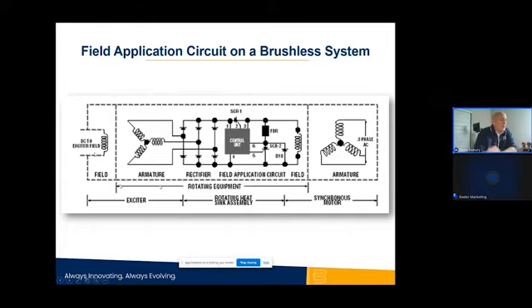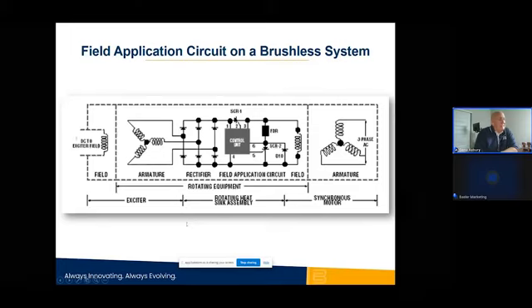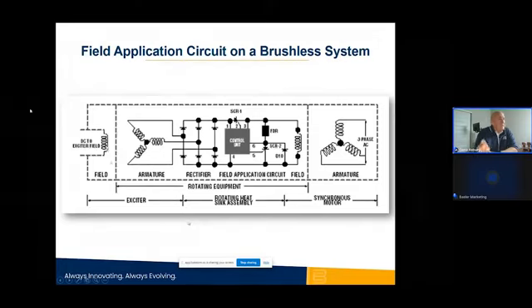And when that field is applied, you're going to get that energy out to the field to pull that motor into step. And at that time, that's when it becomes synchronous. Everything's going like it should. The controller out here is regulating power factor. Now I'm providing excitation to that exciter field to maintain that power factor regulation set point.